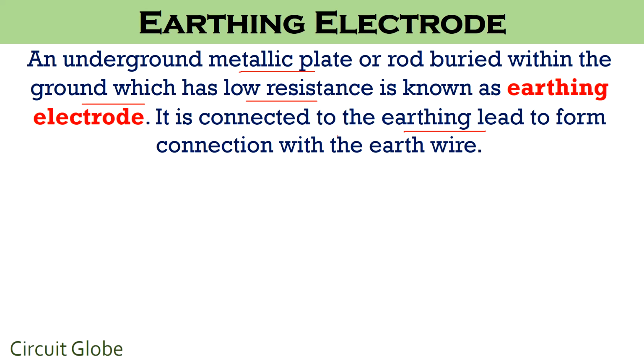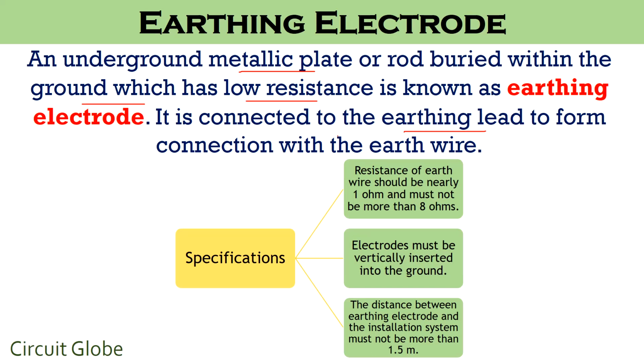To have a properly earthed equipment, there are certain specifications which are required to be considered relative to the earthing wire and electrode, and these specifications are as follows. Firstly, the resistance of the earth wire should be negligible, but practically this is not possible, so it should be nearly around 1 ohm and must not exceed 8 ohms. Secondly, the electrodes must be inserted in vertical orientation into the ground. And lastly, the distance of separation between the earthing electrode and the installation system must not be more than 1.5 meters.